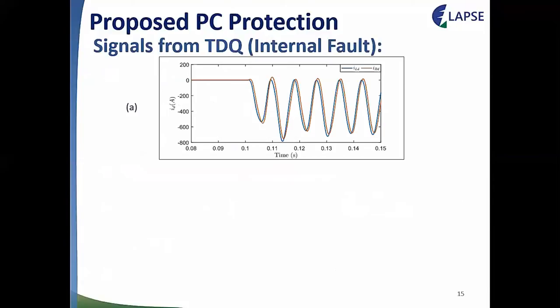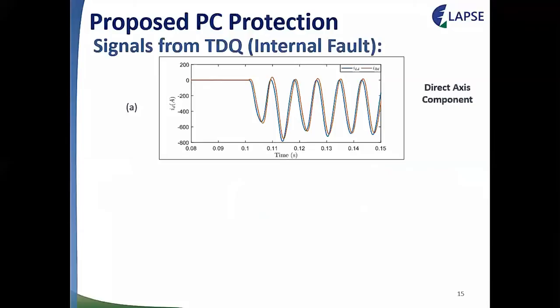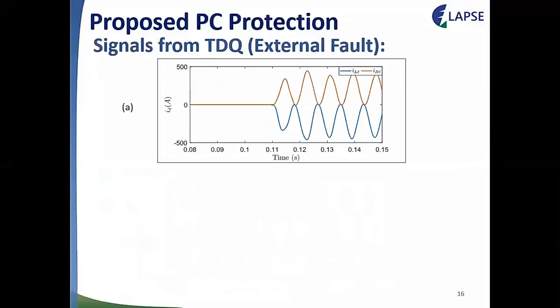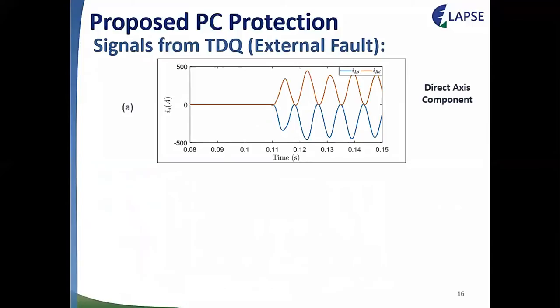When a fault occurs, a DC level superimposes on the oscillating component. To eliminate this, it is proposed to calculate the derivatives of the signals to remove the DC offset from the fault signals. For the study performed, only the derivative of the direct axis current is used, knowing that the quadrature axis current would yield the same conclusions from a protection standpoint. The figure presents signals resulting from TDQ when an internal fault occurs, showing the direct axis component and its derivative — in an internal fault the signals are in phase as expected. For an external fault, the signals are in counter phase.